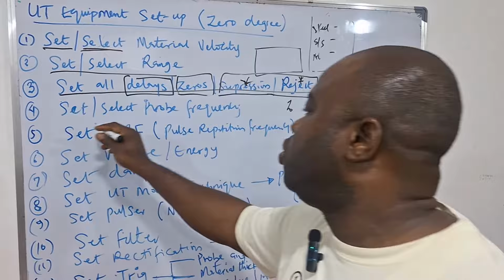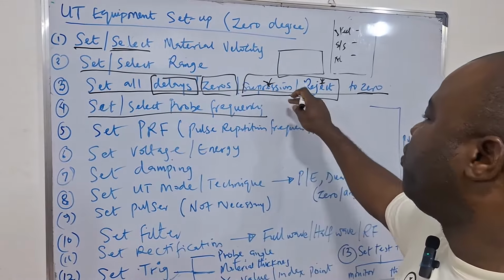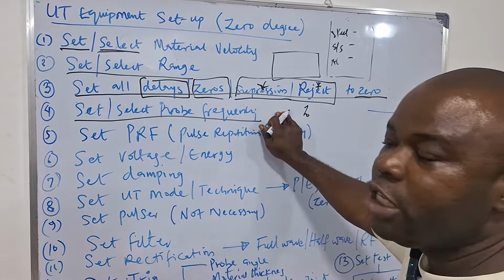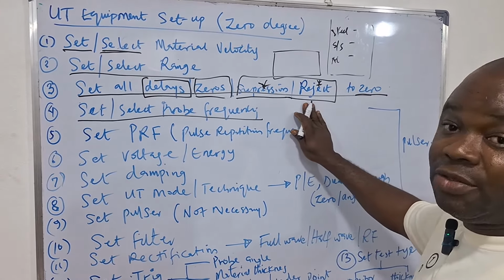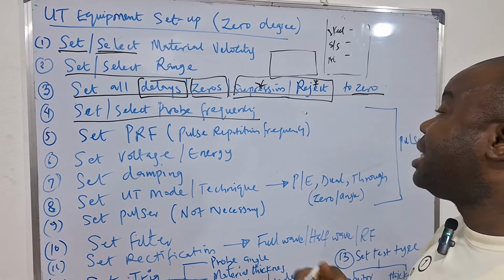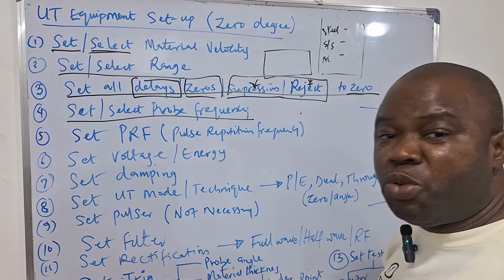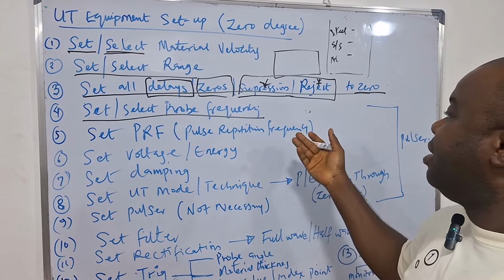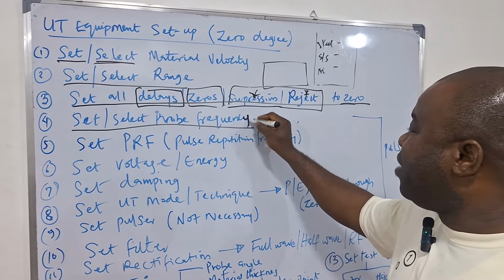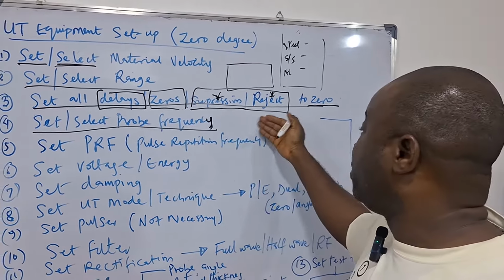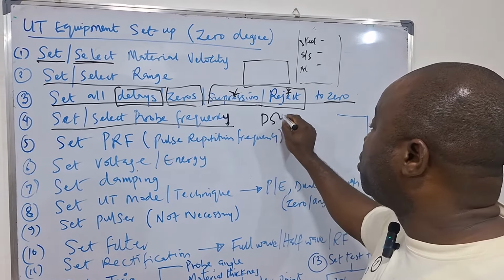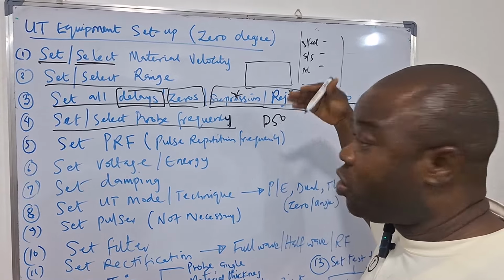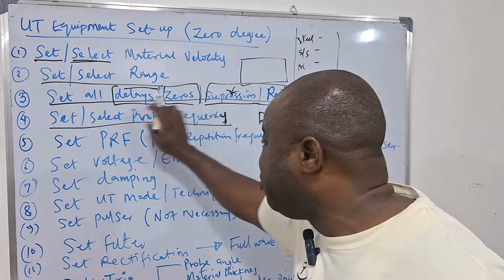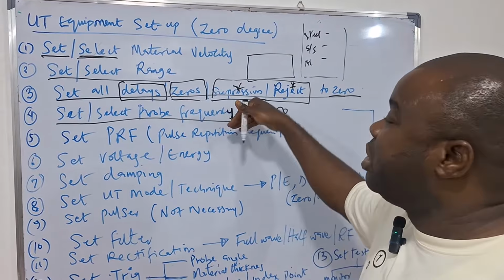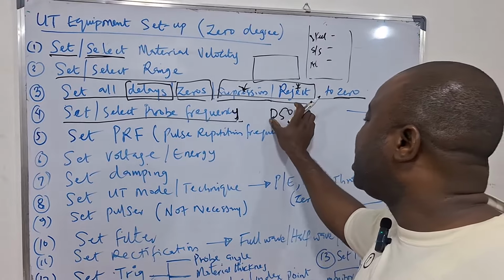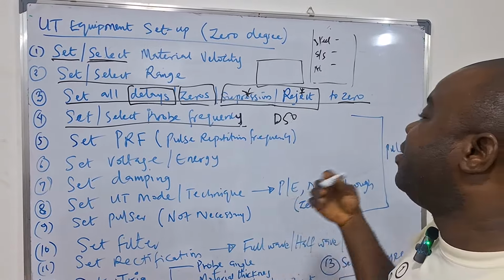Then the next thing you need to look at is to set the probe frequency. There are some UT units that have broadband frequency. In that case, you don't have to set frequency. Immediately you connect your probe, the machine will just work based on the available frequency in the unit. So there is no limitation to that for those that use broadband. An example is your Sonatest D50. It has a broadband frequency, so you won't see any button that will require you to select or to set frequency. But in other cases, you need to select the frequency of your probe.